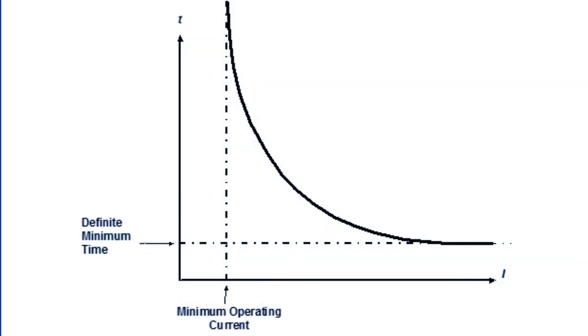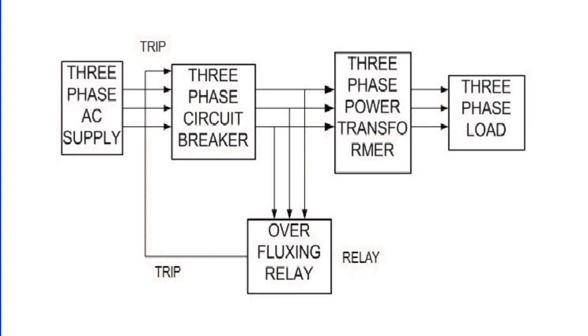Next, we have over-fluxing protection. Over-fluxing, or over-excitation, can cause overheating and core saturation to the transformer. This is where an over-excitation relay comes in handy, preventing transformers from operating at excessively high voltage or too low frequency.